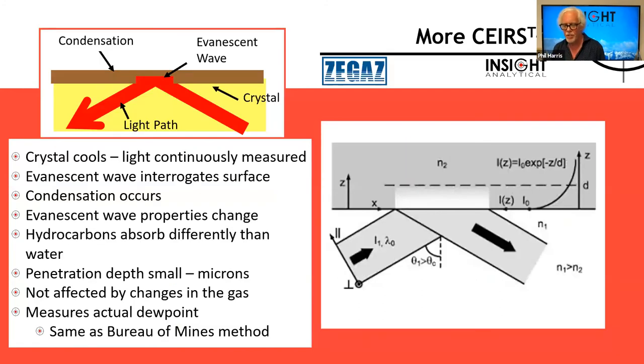So crystal cools, light's continuously measured. The evanescent wave is interrogating, asking the surface, anything out there? Hydrocarbons absorb differently than water. And when we see the dew point, when we hit that temperature, suddenly we get an absorption of the light, and we know we're at the dew point. This is measuring the actual dew point. This is the same as the Bureau of Mines method.